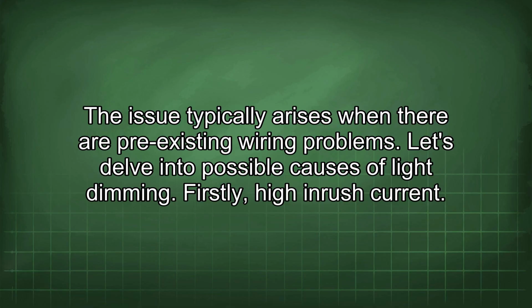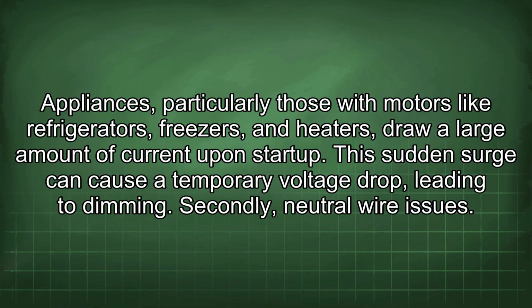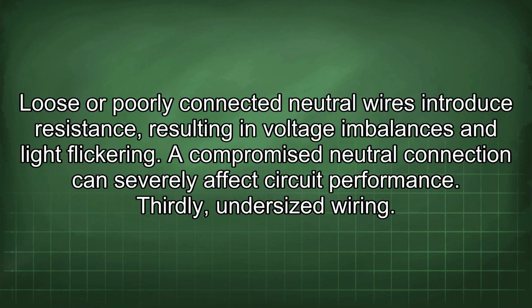Firstly, high inrush current. Appliances, particularly those with motors like refrigerators, freezers, and heaters, draw a large amount of current upon startup. This sudden surge can cause a temporary voltage drop, leading to dimming. Secondly, neutral wire issues. Loose or poorly connected neutral wires introduce resistance, resulting in voltage imbalances and light flickering. A compromised neutral connection can severely affect circuit performance.